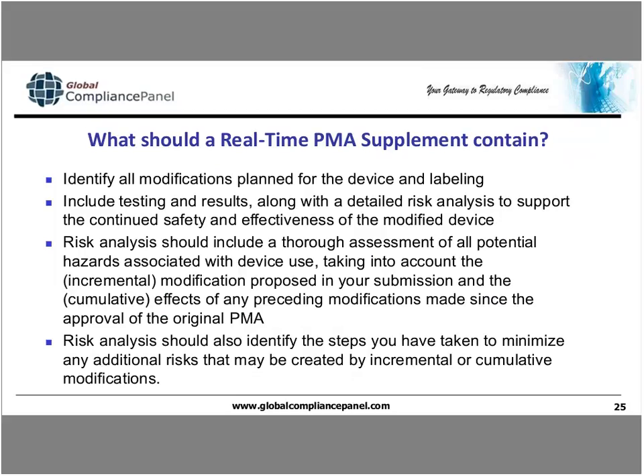What should the real-time supplement contain? Identify all modifications planned for the device and labeling, include testing and results, along with a detailed risk analysis to support the continued safety and effectiveness of the modified device. Risk analysis should include a thorough assessment of all potential hazards associated with device use, taking into account the incremental modification proposed in your submission and the cumulative effects of any preceding modifications made since the approval of the original PMA. Risk analysis should also identify the steps you have taken to minimize any additional risks that may be created by incremental or cumulative modification.